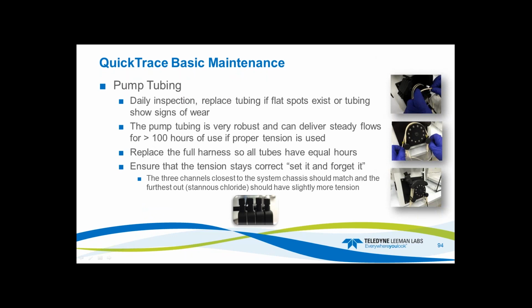Okay, replace it if flat or if they appear worn. And again, it's very robust, that pump tubing, so you should get greater than 100 hours of use if the tension is set properly. In the manual, there's detailed information on how to set pump tubing and also additional troubleshooting information and more tidbits on method development. It's all in there. It's written and very user-friendly. So again, replace the full harness.